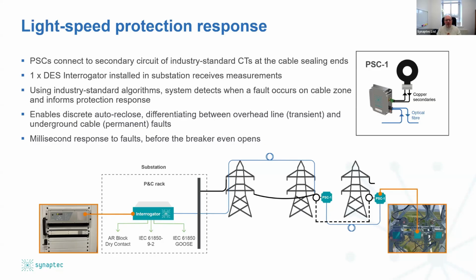It's the right way to think about it. We're just deploying the logic of line differential protection to create a multi-zone protection response and improve how the protection scheme responds to a fault by being more specific about where it's occurring and changing the response according to where that happened. Now, this actually is a pretty typical circuit that we've seen, and you can see a picture of the sensors on the transition tower there.